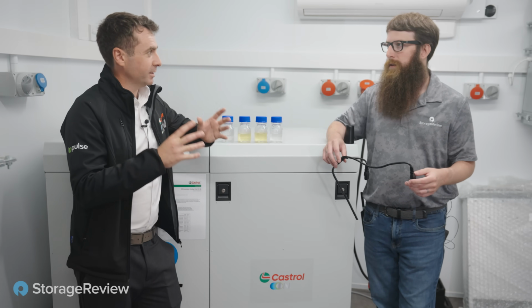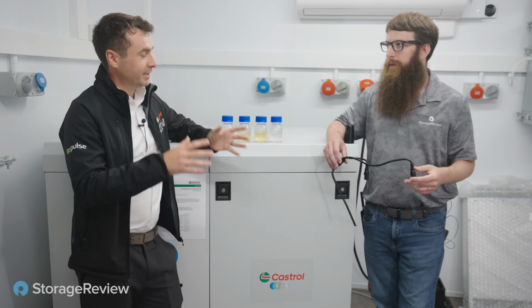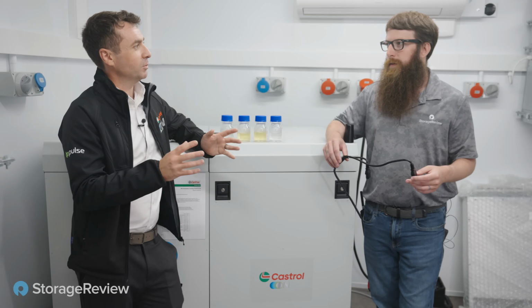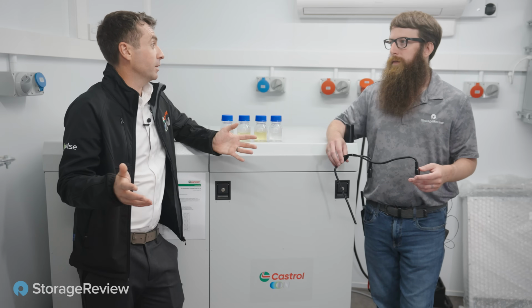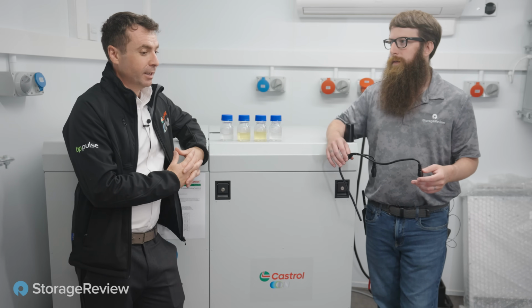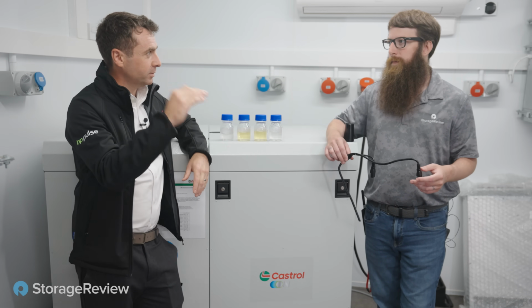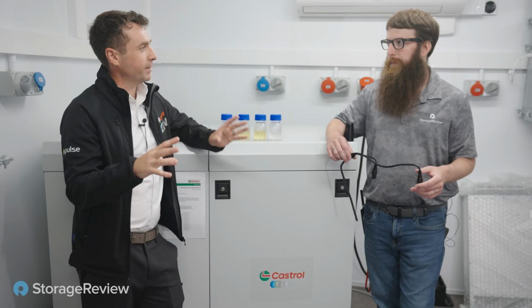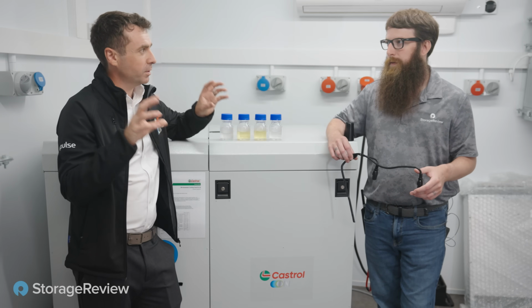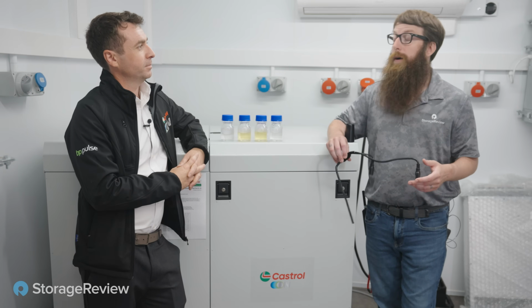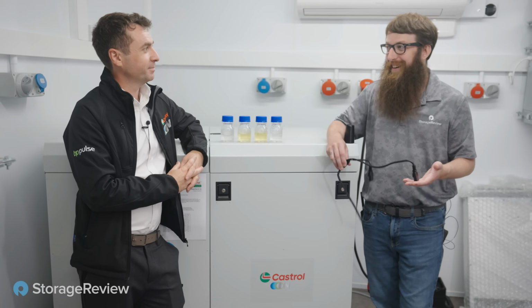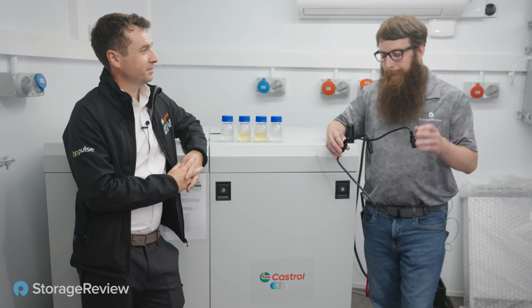The power the CDUs require for pumping fluid around is still far less than the fan consumption on an air-cooled server, or even a direct-to-chip server that still has fans on. In one rack-based immersion scenario, 500 watts of fans are removed and replaced by two 30-watt pumps. That's a pretty big saving.